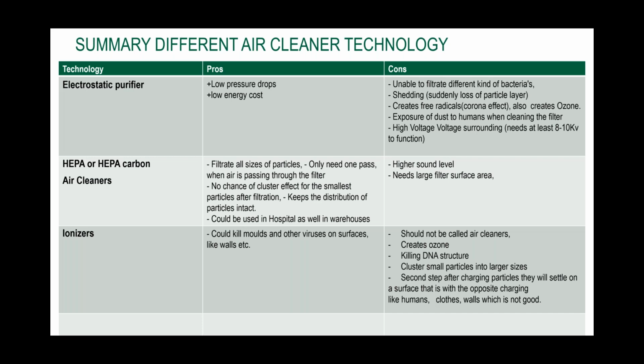HEPA or HEPA carbon hybrid air cleaners. Again, as we looked at with HEPAs, they typically filter all sizes of particles. You only need one pass through the HEPA. There's no chance of cluster effects for the smallest particles after filtration, and it keeps the particles in the filter. And these can be used in hospitals, pharmaceutical environments, as well as warehouses, offices, etc.